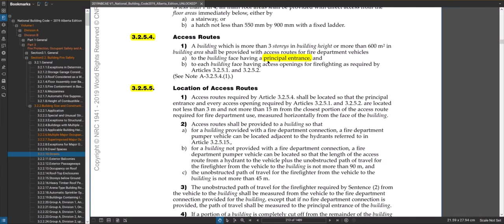Section 3.2.5.4 essentially tells you that a building in Part 3 — one that's over three storeys in building height or more than 600 square meters in building area — shall be provided with access routes for fire department vehicles to the building face having a principal entry. Most buildings have a principal entry, and you have to identify that entry as the principal entry for fire department purposes. That's essentially where the truck is going to head when there's a fire.